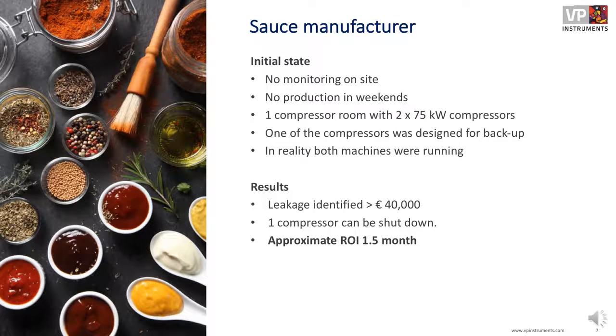This sauce manufacturer also worked without monitoring. It had no production on weekends, and one compressor room with two 75 kilowatt compressors - actually, one was designed for backup use, but in reality both machines were running. When we started to measure with some basic monitoring and metering, we identified 40,000 euros of leakage, equivalent to 50,000 US dollars. We also saw that one compressor could actually be shut down if we took out all the leakages. We calculated the return on investment at about 1.5 months.